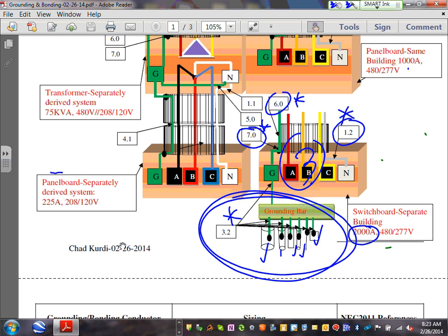What is that? A bunch of ground rods in the ground and you tie to them. Or the foundation of the second building, if it's concrete or steel, you have to tie to it, right? The water coming to the second building, you have to tie to it. Exactly, Adam, like we do at the service. Exactly like we do at the service, we do it at the second building. Okay? Shall we go size these three for the separate building, guys?